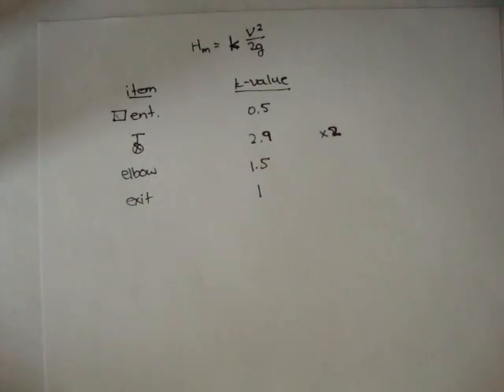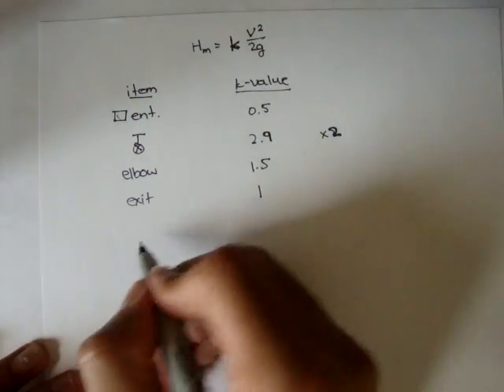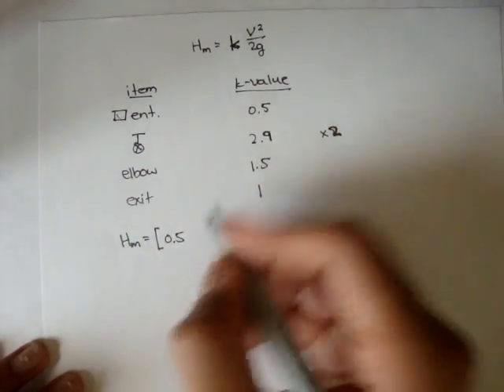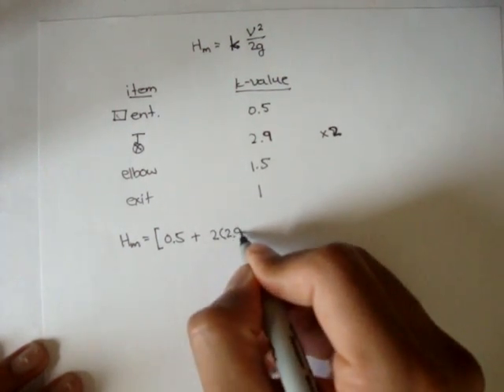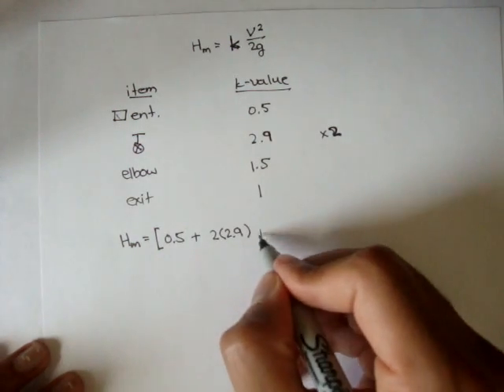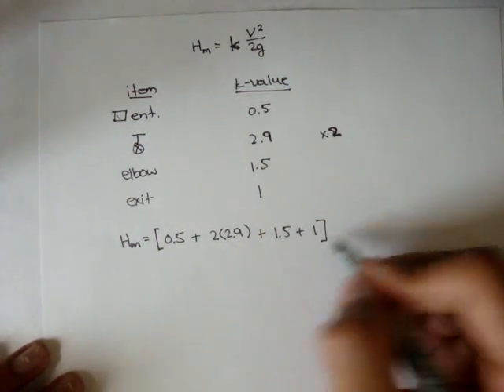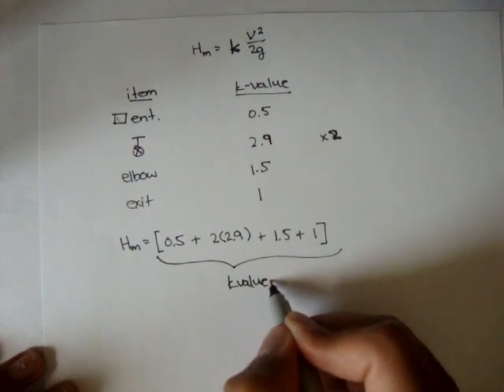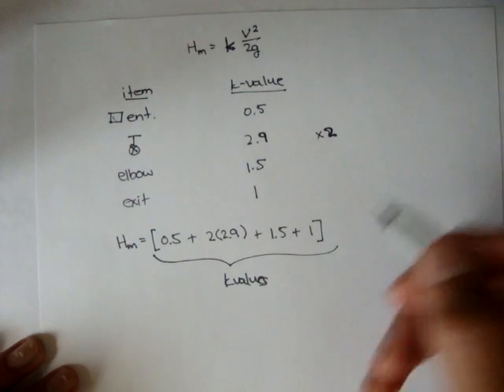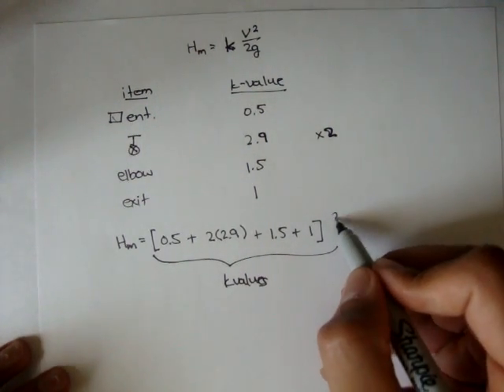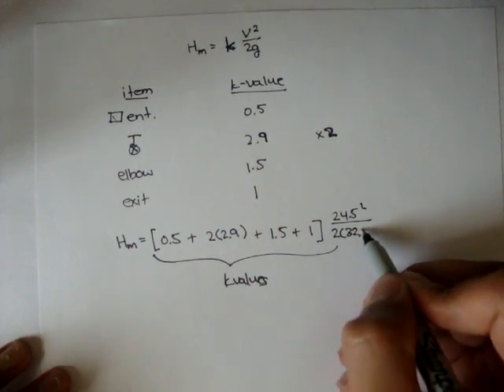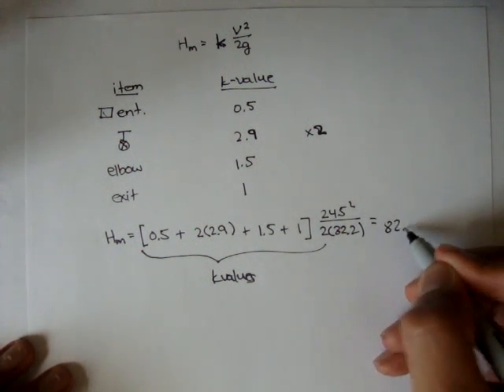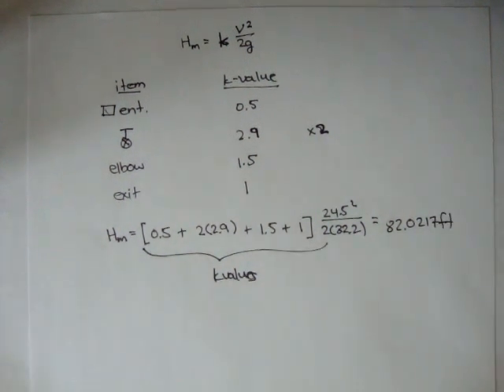So if we take these k values and plug it into this formula to find the minor losses, we can say the h minor is going to be all of the k values, so 0.5 plus 2 times 2.9, right, because there's two fully open check valves, plus the 1.5 for the elbow, plus the one for the exit. And the velocity - so this is all the k values, minor loss coefficients - and we multiply that by v squared over 2g, and the v squared over 2g is 24.5 squared over 2 times 32.2. And if we solve all this out, we get that the minor losses are 82.0217 feet. That's the minor losses.